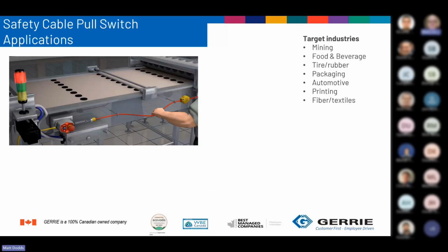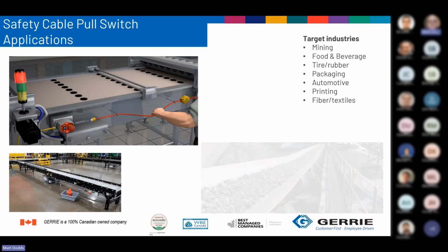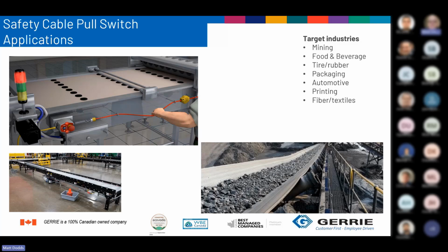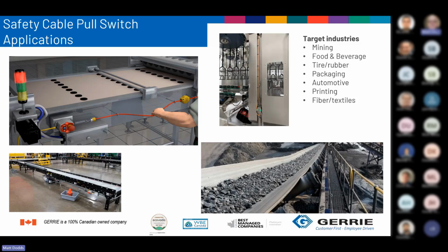So good application for cable pull, conveyors, tables. Pretty much, every conveyor needs a cable pull switch. Sometimes around the opening of a piece of equipment that has kind of full access, maybe there's some rollers or something there that need to be cleaned, like say a printing press or something. Or I've seen them in paper making applications where you got two rollers coming together. Someone needs to be in there for inspection or something. So they have these openings guarded with a cable pull switch.